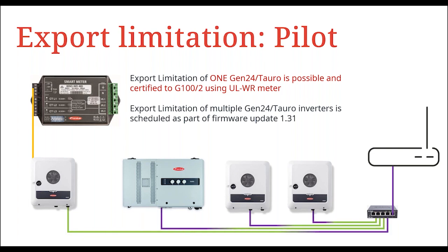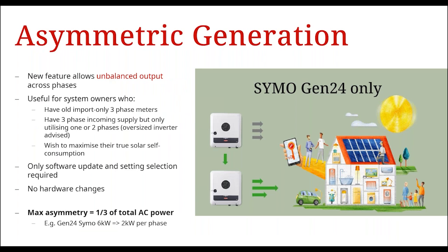This means that we can have larger systems which are export limited and controlled by that one master inverter. This will also be possible using the older Snap inverters. So if you have a data manager, the data manager can receive the signal as well. The key thing is that the master unit must be a Gen24 or a Tauro with the latest control software.